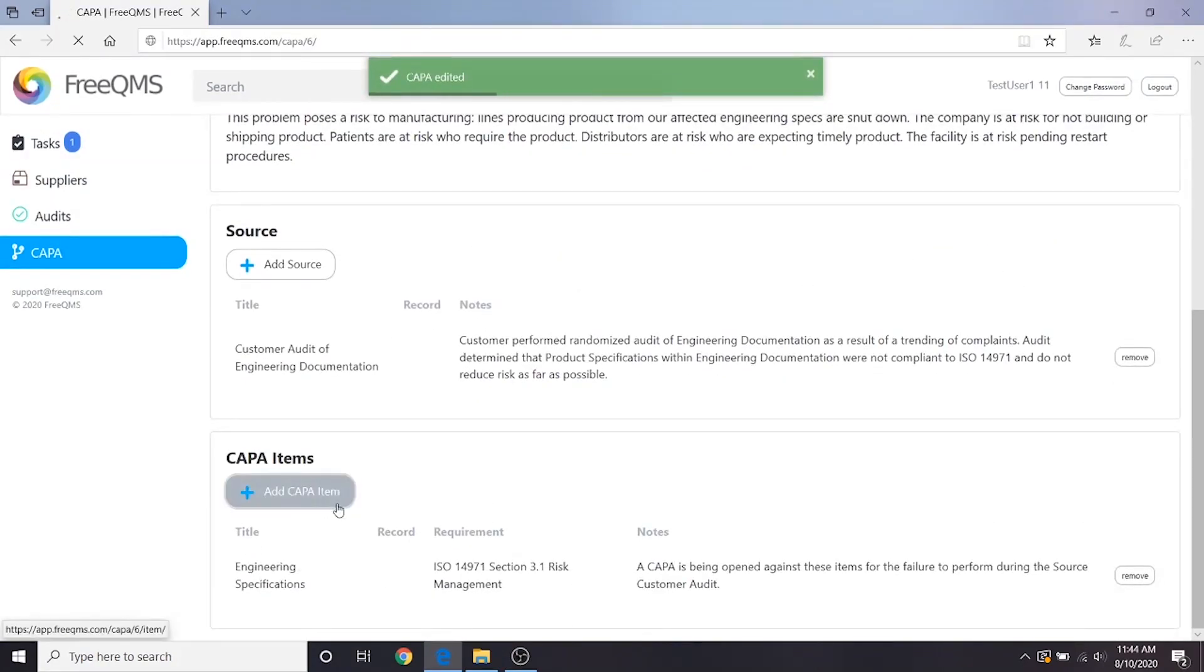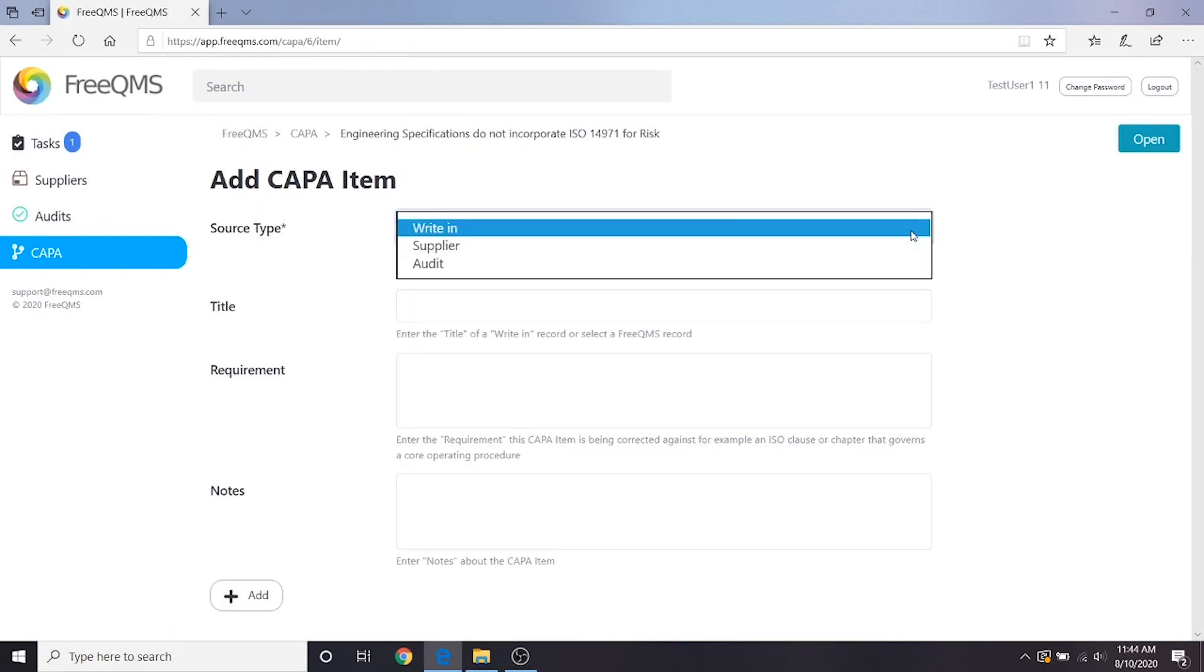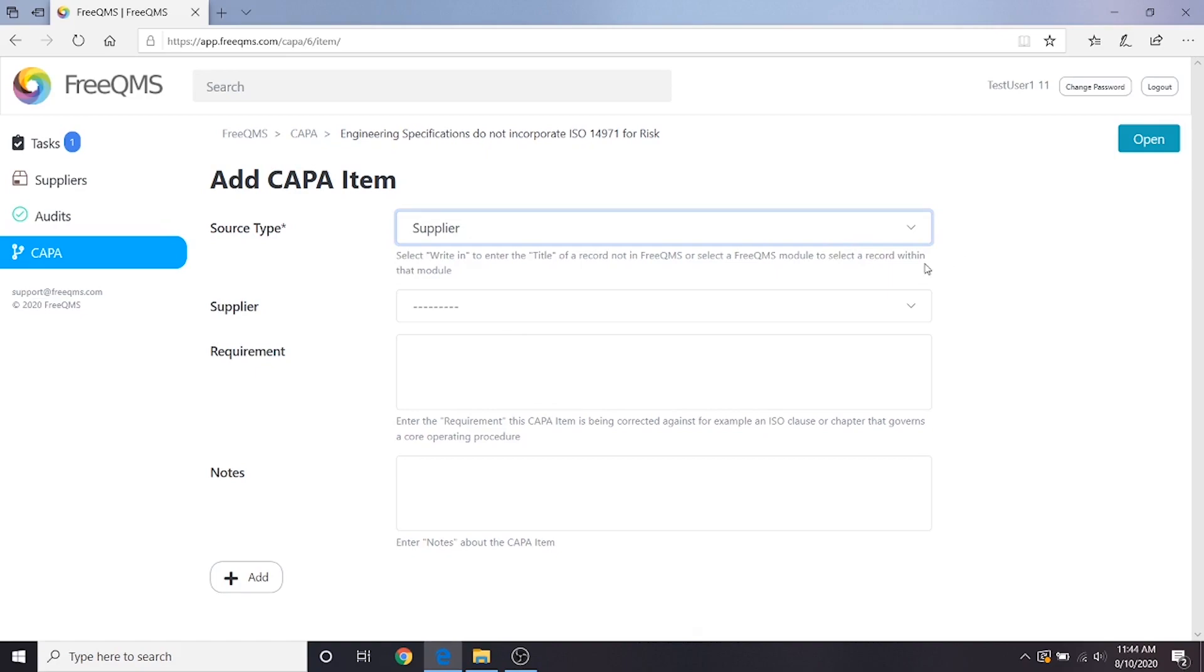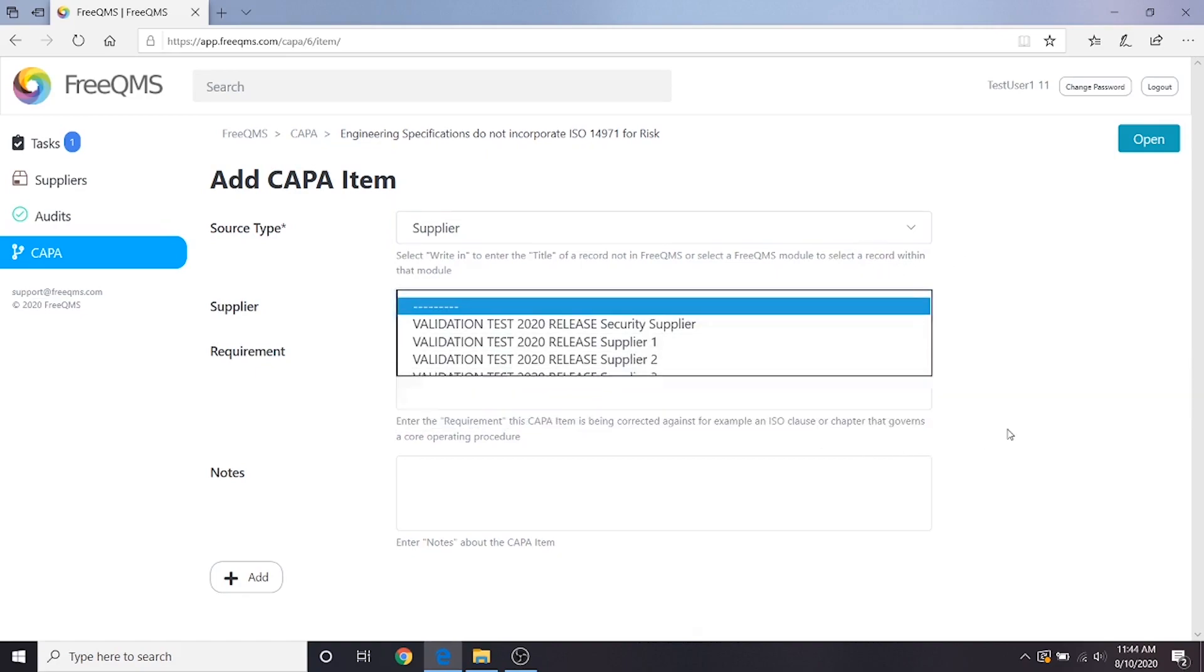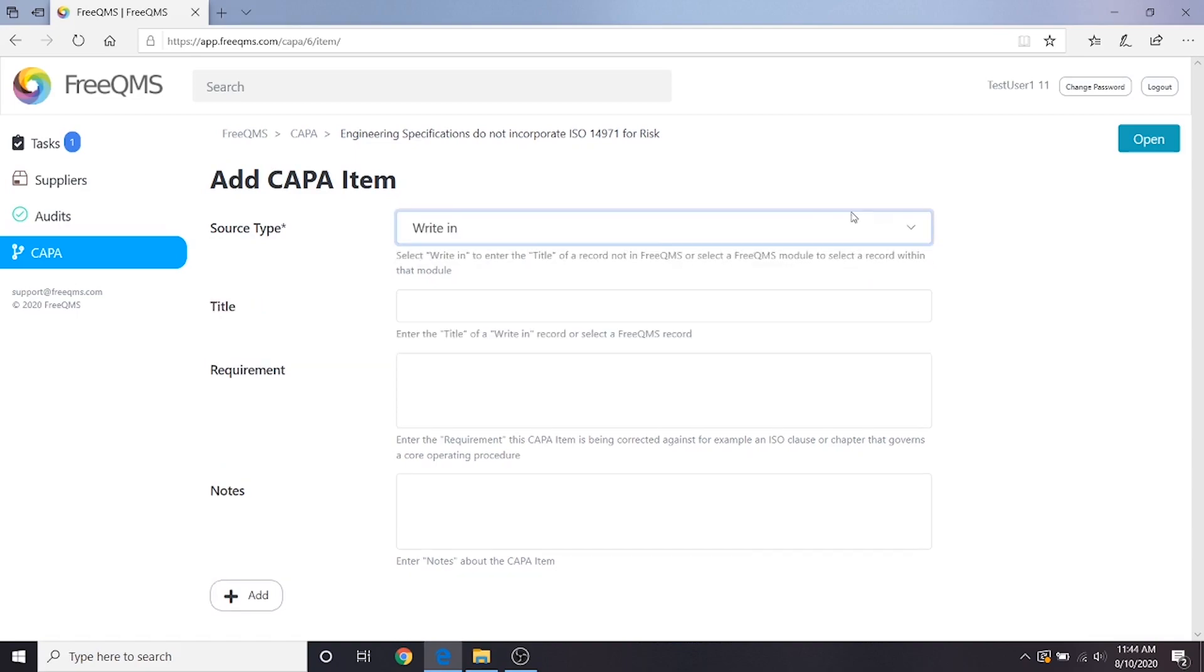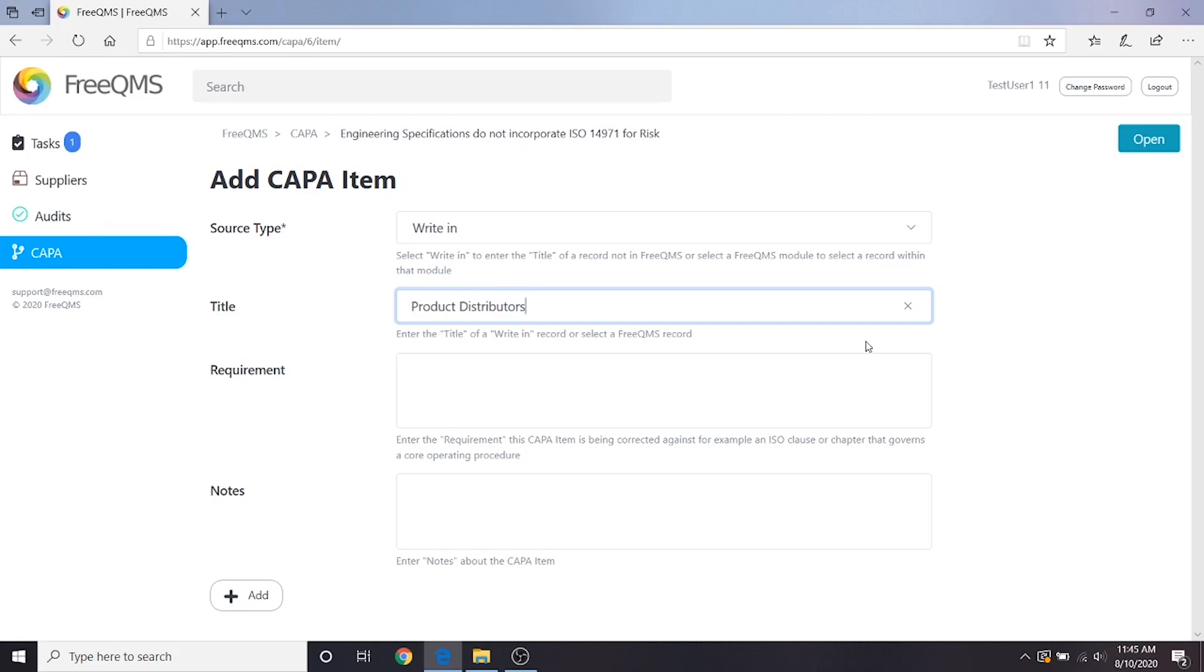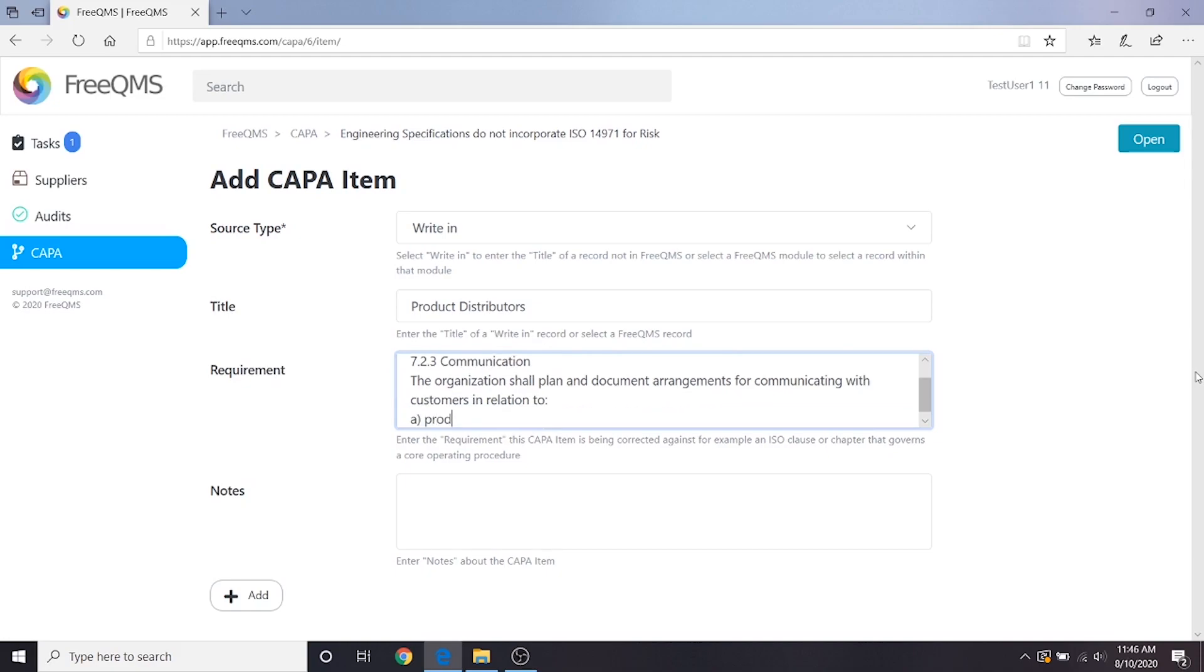Let's click add CAPA item. In a real world scenario, we would likely change the top field to supplier and then select each distributor affected by this CAPA. Since this is an abbreviated demo, we will leave the top selection as write-in and then enter product distributors in the title field. Although there are many options here, our fictional company is compliant to ISO 13485, so for requirement we will enter ISO 13485:2016. We have a procedure for notifying customers, in this case distributors, of problems with our product. Under notes we'll put: create action to notify distributors.